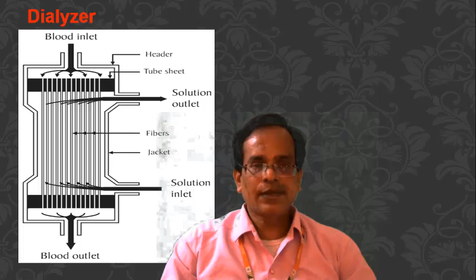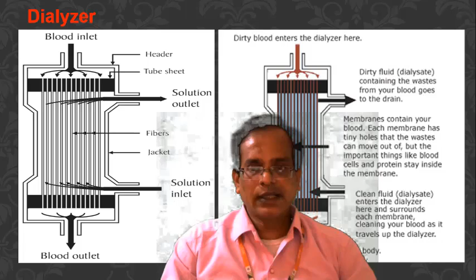So here, the dirty blood enters the dialyzer at the blood inlet, and the dirty fluid, the dialysate containing the waste from your body, goes to the drain. Membrane, next stage, contains the human blood. Each membrane has tiny holes that the waste can move out of, but the important thing is that blood cells and protein stay inside the membrane. The third stage, the clean fluid, that is the dialysate, enters the dialyzer here and surrounds each membrane, cleaning the blood as it travels up the dialyzer. So clean blood is returned back to the human body.